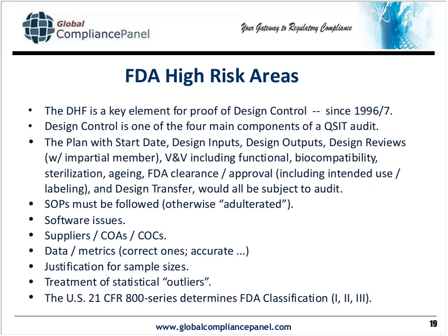Do you know what that equipment is? Do you know if it's been validated? Do you know if it's calibrated? Do you know if the people are trained? Do you know if it's defined by an SOP? And if it's a critical element and you're accepting it on one of those certificates, you probably need to do a site audit or contract for a site audit to make sure that the documentation means what it says and it hasn't been just pencil whipped.